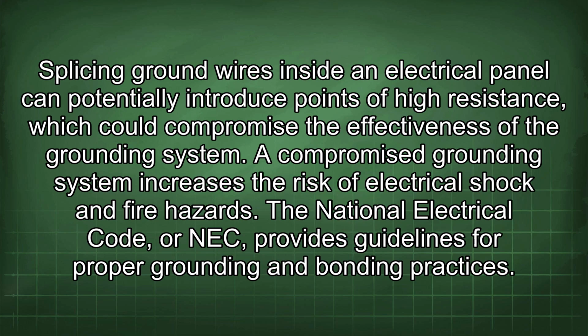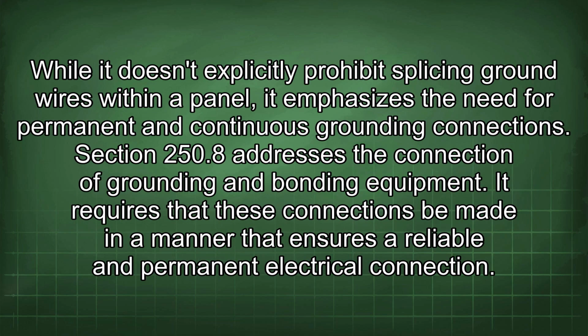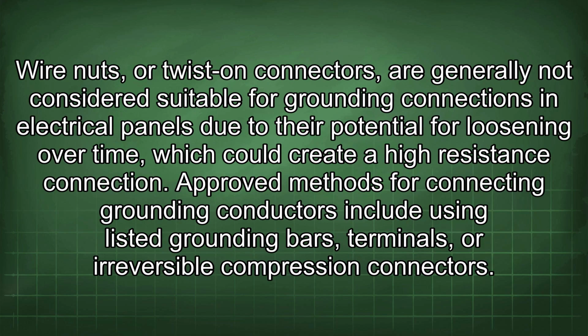The National Electrical Code, or NEC, provides guidelines for proper grounding and bonding practices. While it doesn't explicitly prohibit splicing ground wires within a panel, it emphasizes the need for permanent and continuous grounding connections. Section 250.8 addresses the connection of grounding and bonding equipment. It requires that these connections be made in a manner that ensures a reliable and permanent electrical connection. Wire nuts or twist-on connectors are generally not considered suitable for grounding connections in electrical panels due to their potential for loosening over time, which could create a high resistance connection.